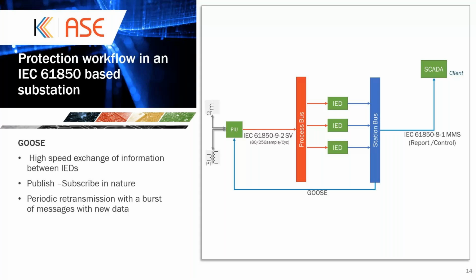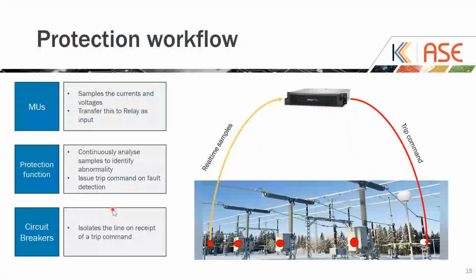So here we talk about GOOSE. GOOSE is the abbreviation for Generic Object-Oriented Substation Event. These are high-speed data exchanges that are used for communicating directly between the IEDs. If an IED wants to send something to another IED, it can use a GOOSE message. Similarly, a trip message can be sent as a GOOSE message to the field. IEDs can publish GOOSE messages for other IEDs, and also subscribe to GOOSE messages from other IEDs. The key point is, we do not have any copper connections coming from the field to the device. All of them are subscribing and publishing to a communication bus. GOOSE also has periodic retransmission to ensure the messages are not missed.